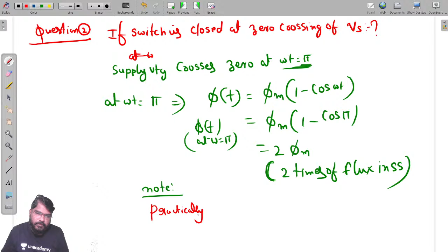Practically the switch is closed in between the minimum value of supply voltage Vs and maximum value of Vs. This is the practical condition. But if the switch is closed at the minimum, zero crossing point, the severity of the transient is very high. If the switch is closed at the instant of maximum value of the supply voltage, the severity of the transient is less.